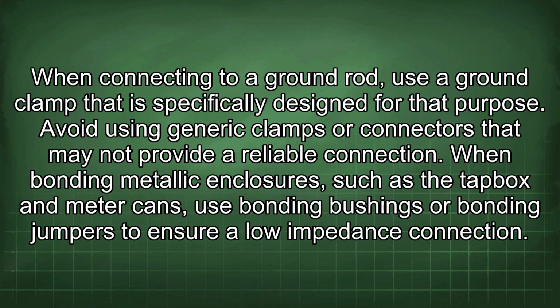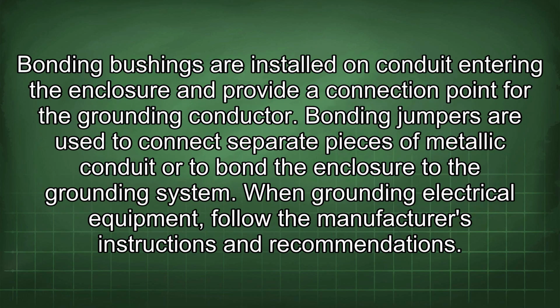When connecting to a ground rod, use a ground clamp that is specifically designed for that purpose. Avoid using generic clamps or connectors that may not provide a reliable connection. When bonding metallic enclosures, such as the tapbox and meter cans, use bonding bushings or bonding jumpers to ensure a low impedance connection. Bonding bushings are installed on conduit entering the enclosure and provide a connection point for the grounding conductor.